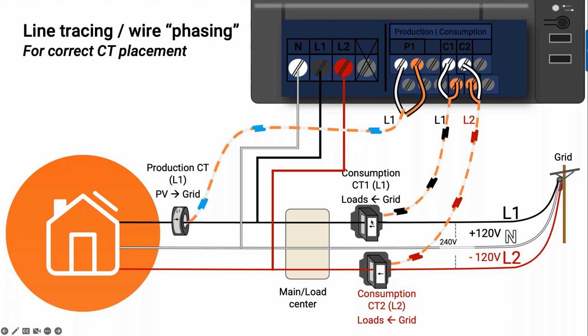So I put 2 CTs in, line 1 CT and line 2 CT, and they get wired into my Envoy, into the line 1 terminal block positions and line 2 in my line 2 terminal block positions. The IQ gateway, which is actually my meter, takes the voltage measurement and current measurement for line 1 and the voltage measurement and current measurement for line 2, and then it does the math, calculates it, and says this is the power for each phase.